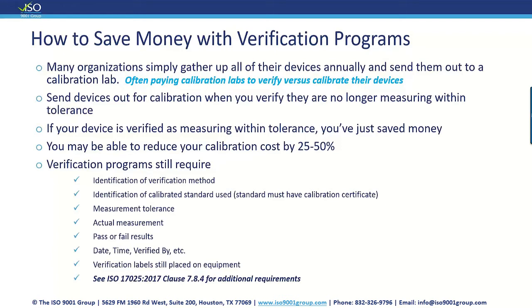You have to identify your verification method, as in the example I gave of putting a calibrated weight on a scale, or using a gauge block that was calibrated, whatever the method is. Secondly, you still need to have the identification of the standard that you use. So that weight needs to still have a number and needs to be traceable. It needs to be verified and calibrated that it is the exact weight that is reported. The standard that you use for verification should have its own calibration certificate.